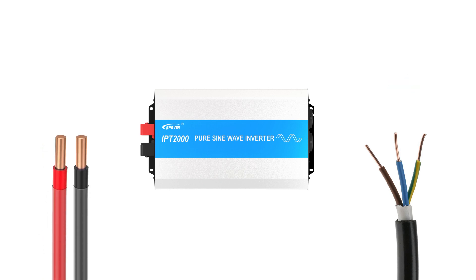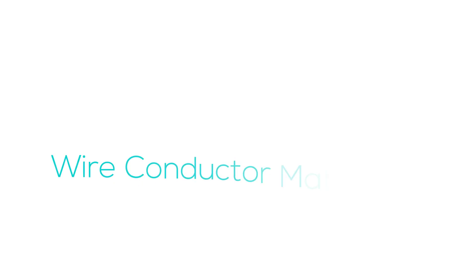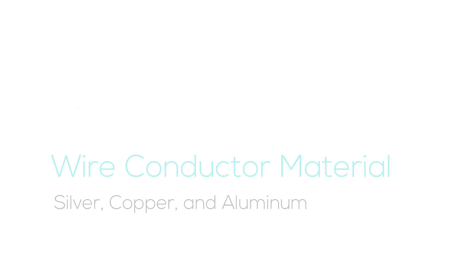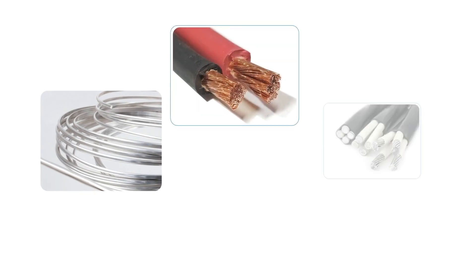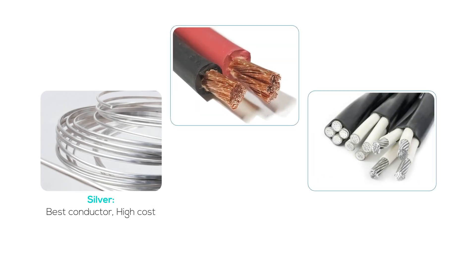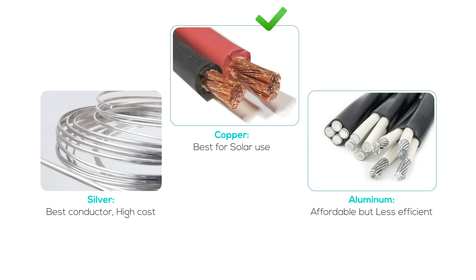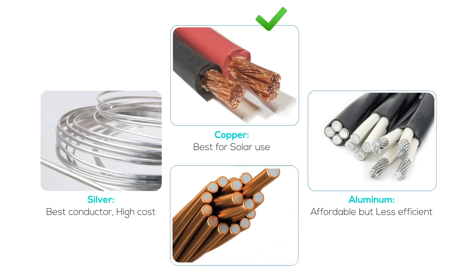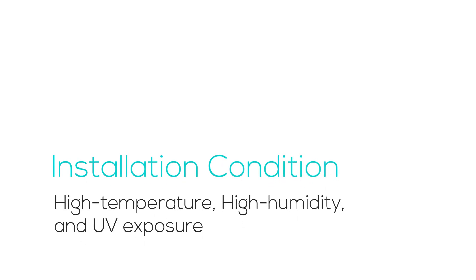On the DC side, avoid using non-flexible cables. In terms of cable materials, there are three main choices: silver, copper, and aluminum. Silver is a top conductor but too expensive for solar use. Copper is the favorite for solar because of its great conductivity. Aluminum, while cheaper, isn't as efficient and can mean more energy loss. Also watch out for copper-clad wires, which have aluminum inside — they can't carry as much current and may break or overheat over time.